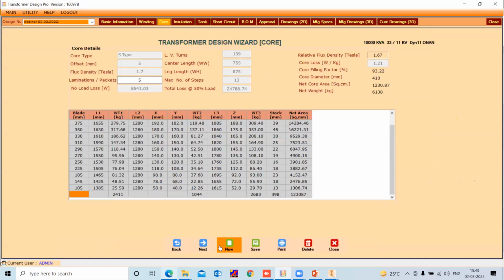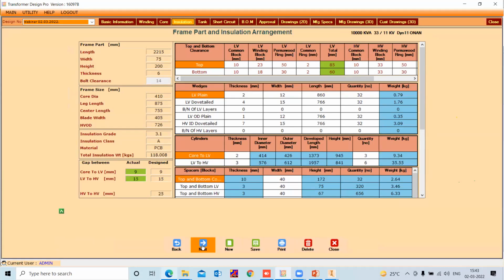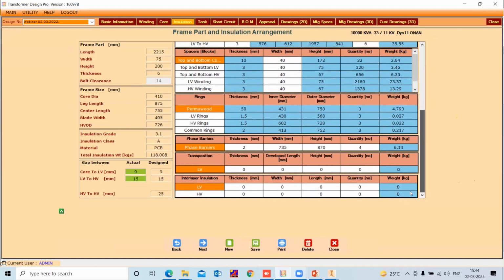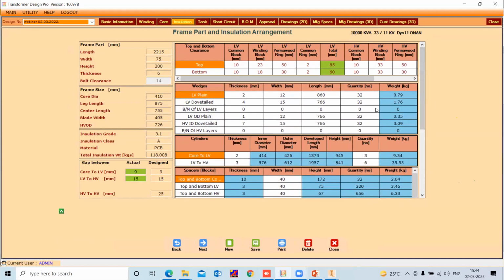This is the core chart. In the printout, you will get all the diagrams for that. This is again the insulation arrangement: how we arrange the insulation, like top and bottom clearances, core to LV gap, LV to HV gap. That information is available on this page, like wedges, cylinders, then the spacers, then the rings, phase barrier, transposition detail, interlayer insulation detail. Whatever values are zero are not applicable for this design, and they will be automatically removed in the reports. So using this white cell functionality, you can make your own insulation arrangement also.